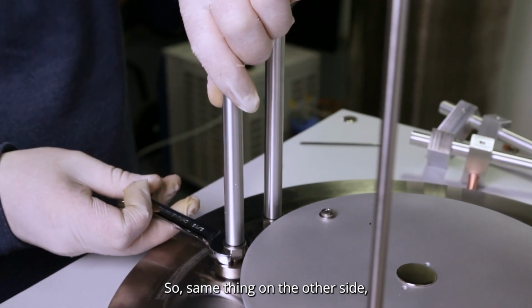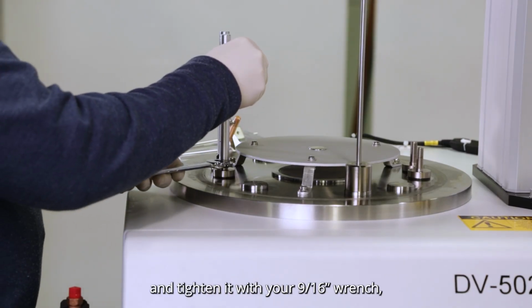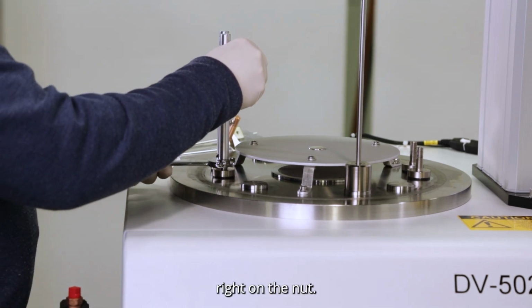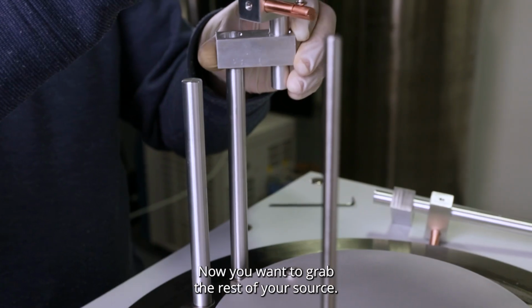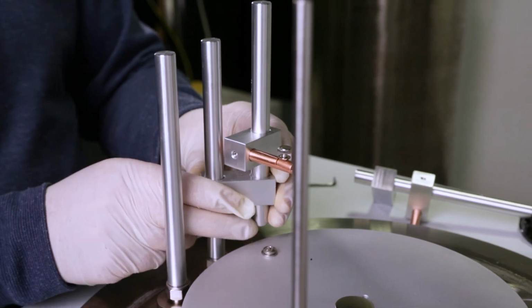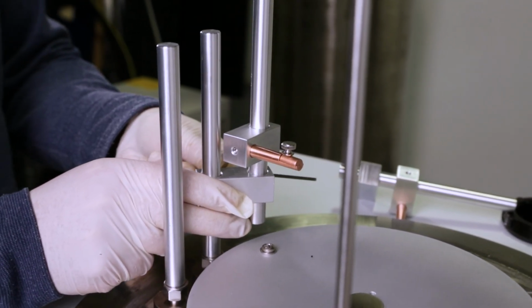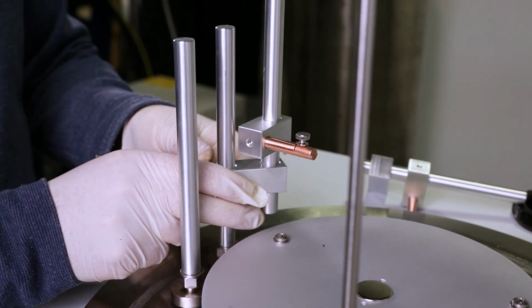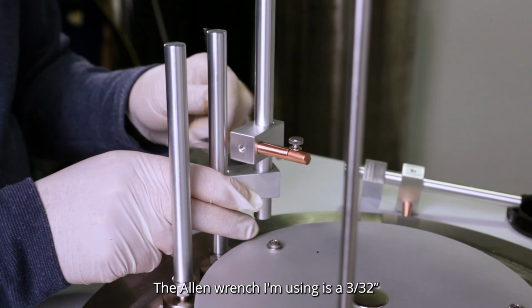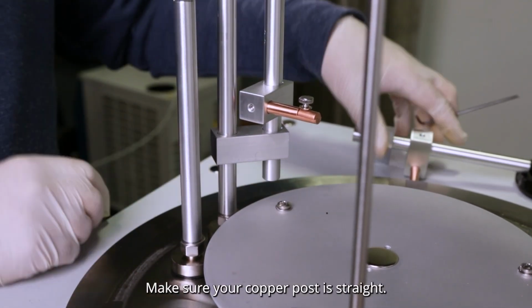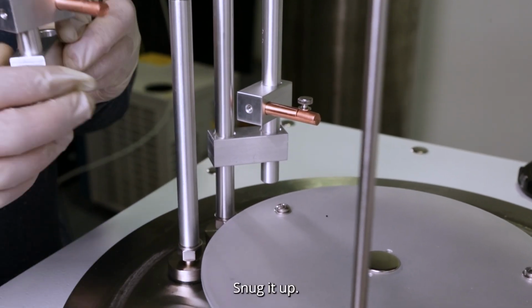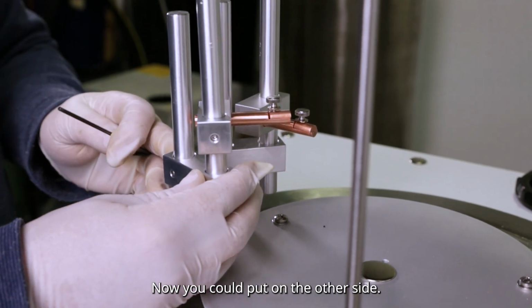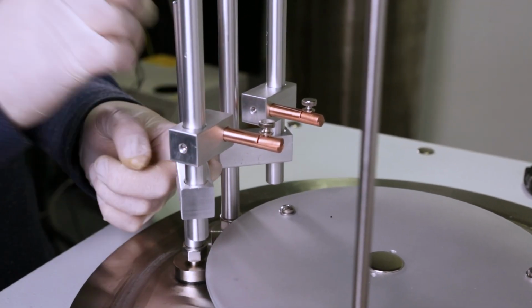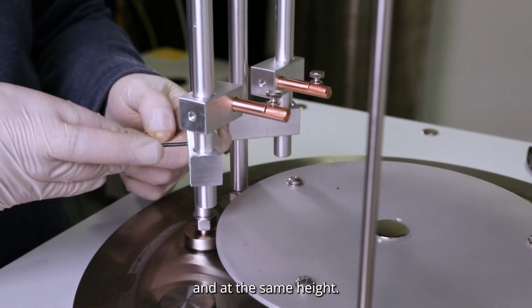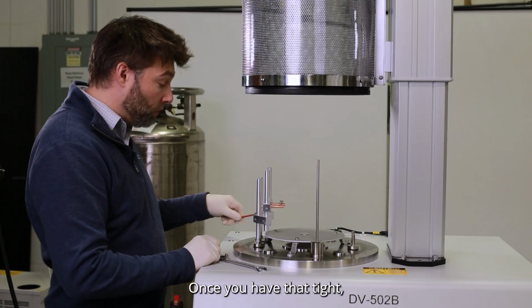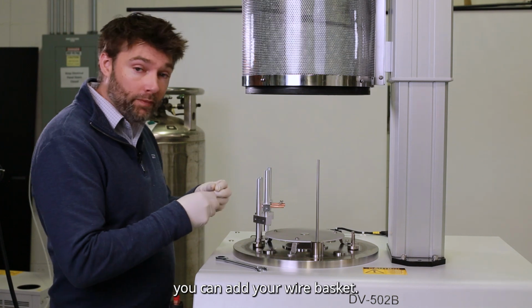So same thing on the other side. Back off the post and tighten it with your 9/16 wrench, right on the nut. Now you want to grab the rest of your source. The Allen wrench I'm using is a 3/32. Make sure your copper post is straight. Snug it up. Now you could put on the other side. Make sure that copper post is straight as well and at the same height. Once you have that tight, you can add your wire basket.